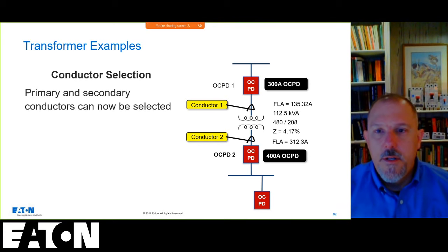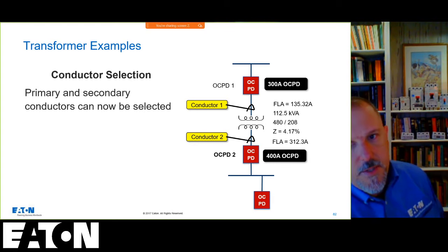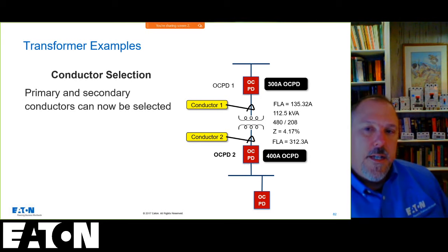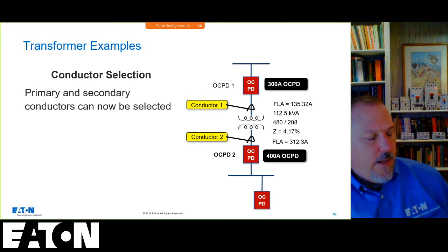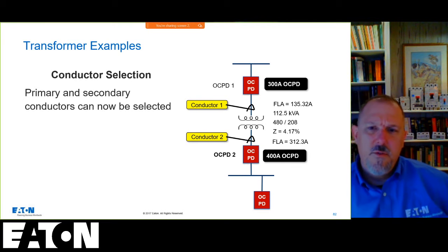Okay, Tom Arns. All right, utility companies can design around diversity of the load. Yep. I'm not sure about that. Wait, aren't small dry type transformers typically 100% rated for continuous loads? That's an interesting point. So I don't know of anything that says I can't use a transformer at its kVA. There's no 100% rated transformers.